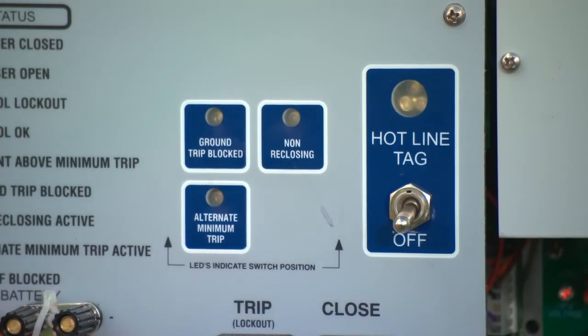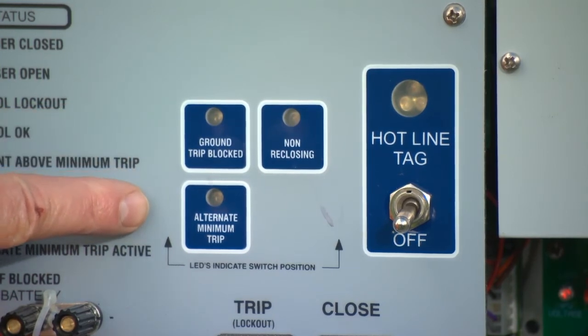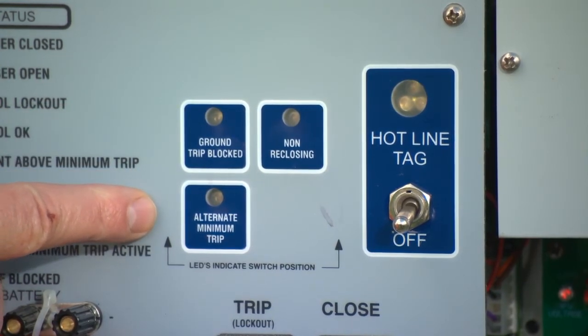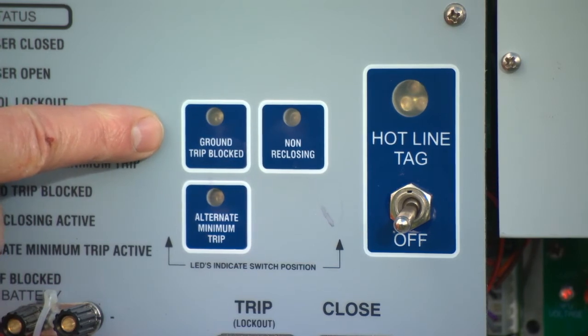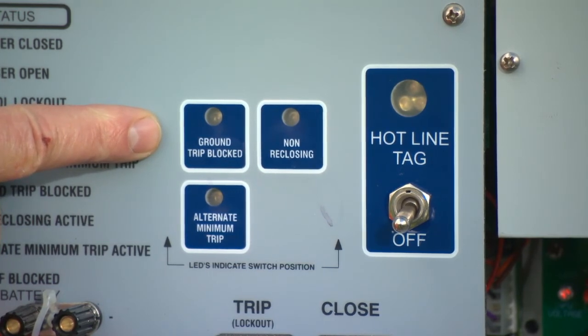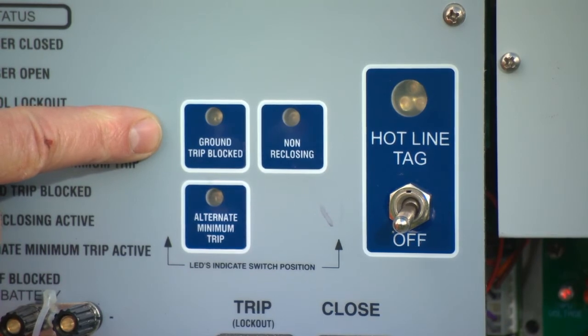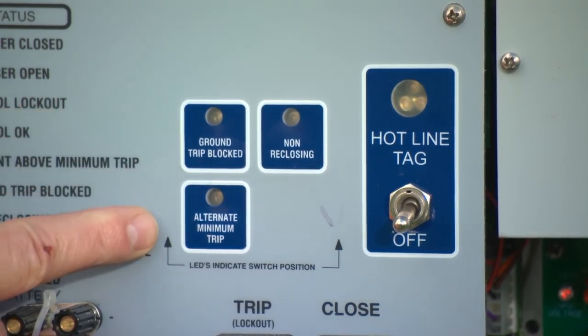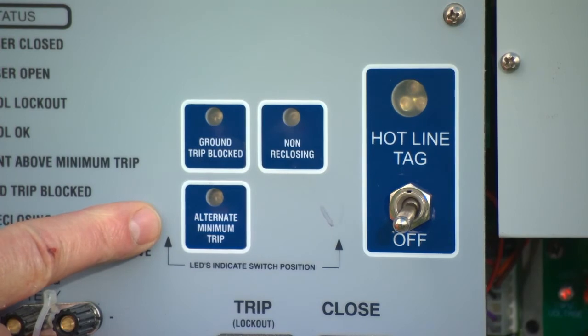Looking more closely in the center of the control, you will notice 3 reference buttons, in addition to the hotline tag switch. These are selection features. On the top left-hand side is the ground trip blocked button. By pressing this button, you will block your ground. Below that you will see the alternate minimum trip button.